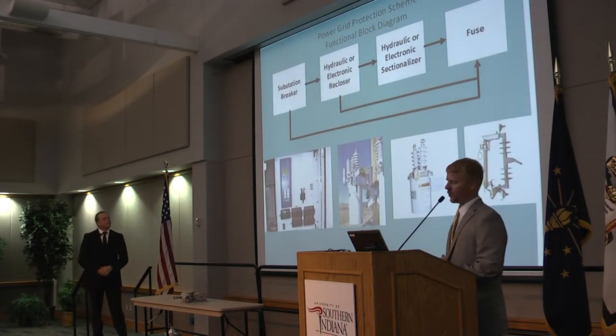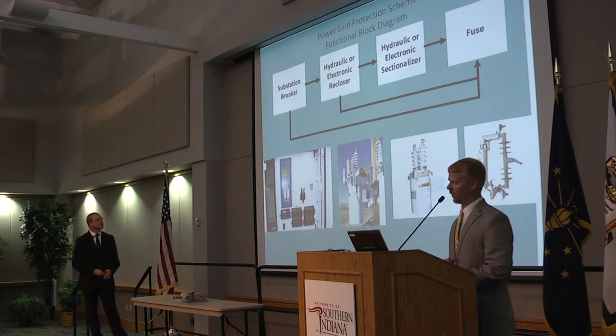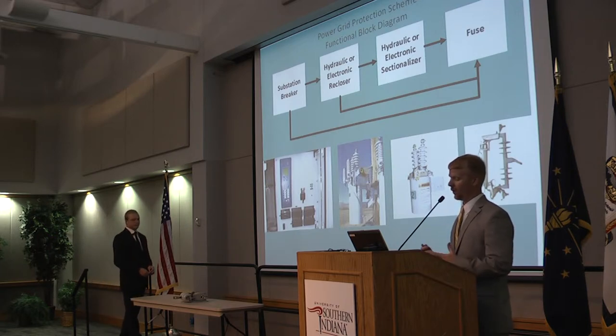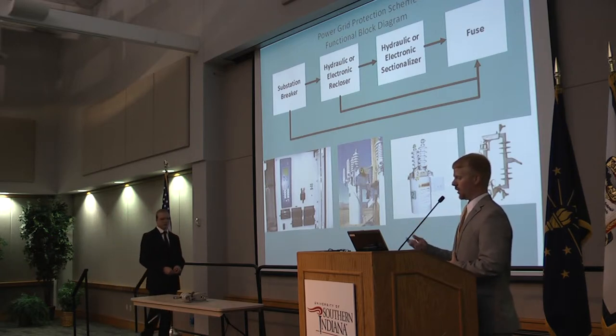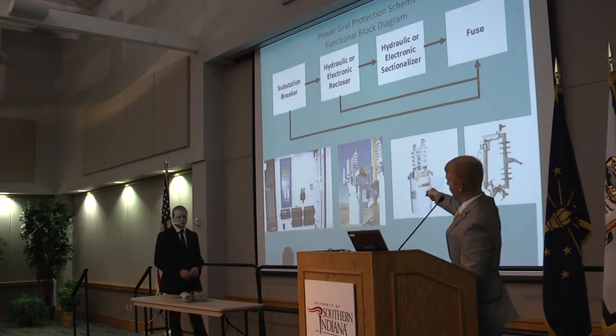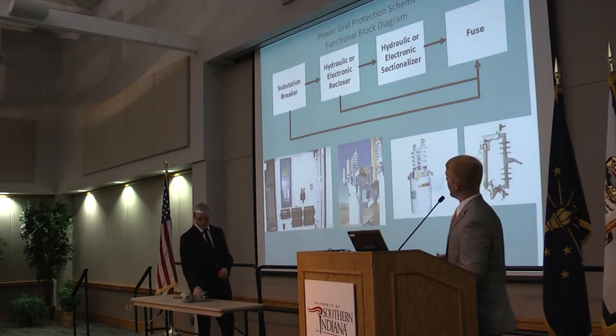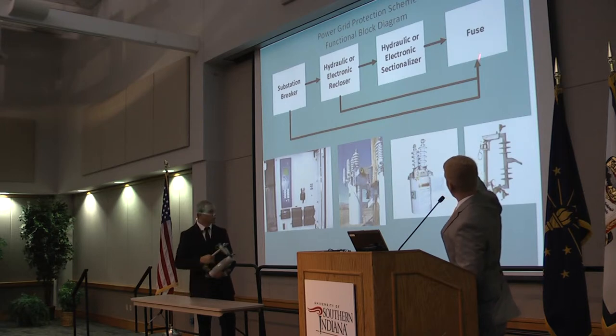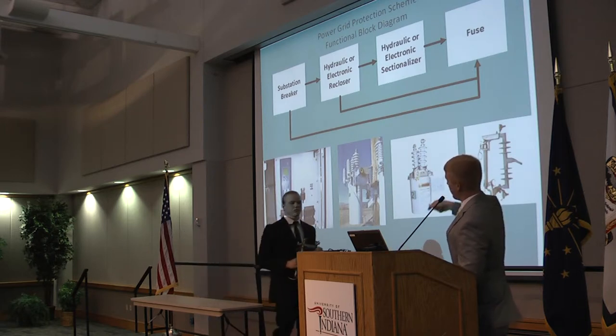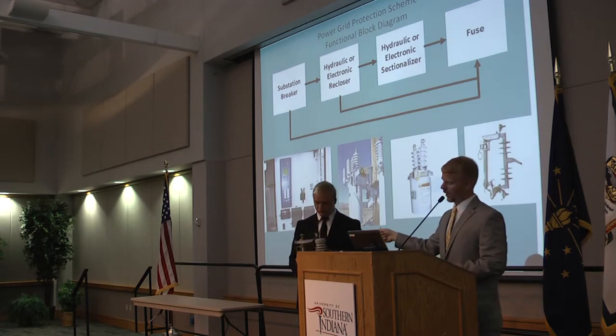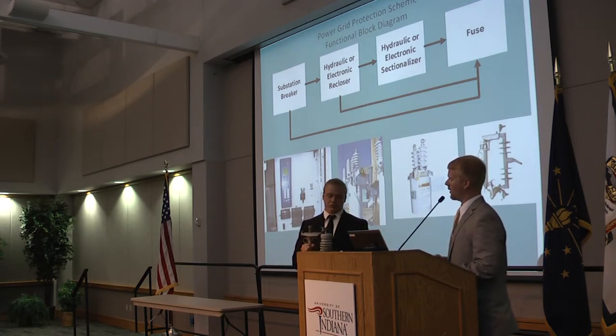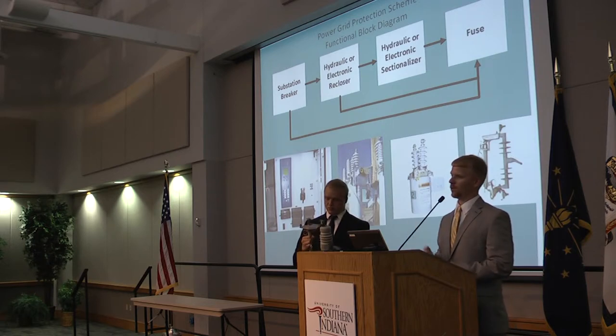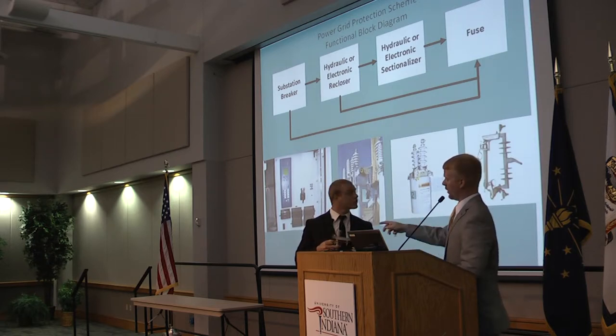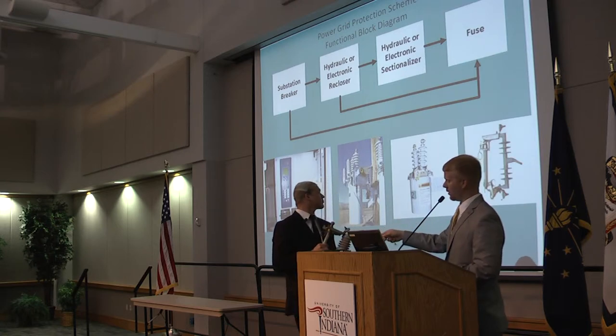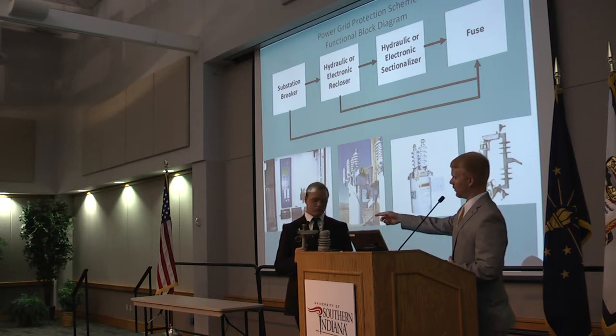So Vectren's protection system, here's another functional block diagram of our protection scheme. This is on a usual circuit. What we try, the perfect layout would be from the distribution substation, there is a circuit breaker, which a picture can be located down here. As you can see up here, each one can feed into a fuse itself, which Zeke is holding. The fuse is a single shot. Basically, if it senses that there's a fault, it will burn the fuse, and there's a chemical reaction that causes an explosion and will actually cause the arm to fall.